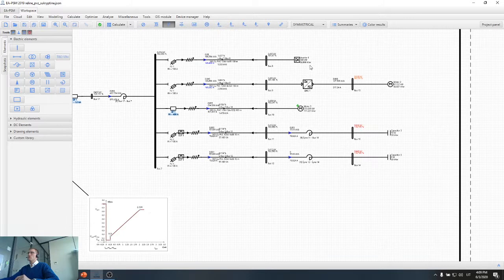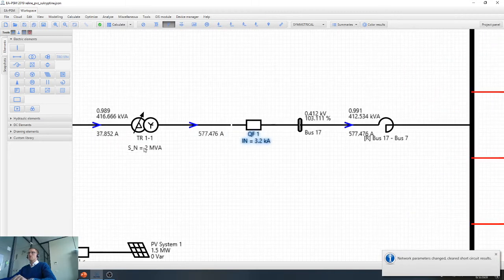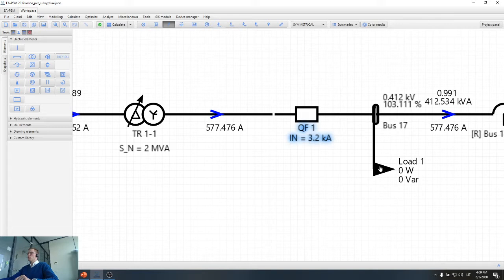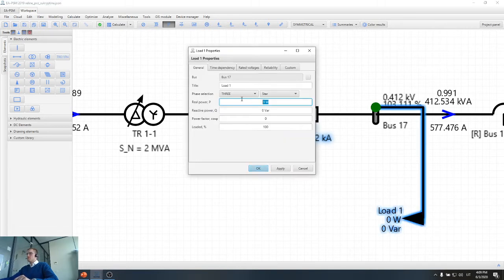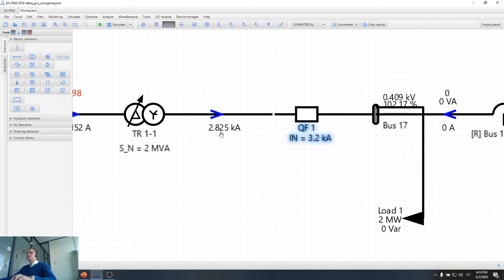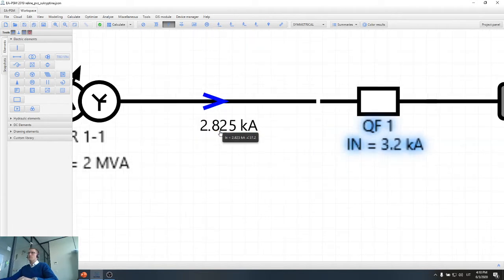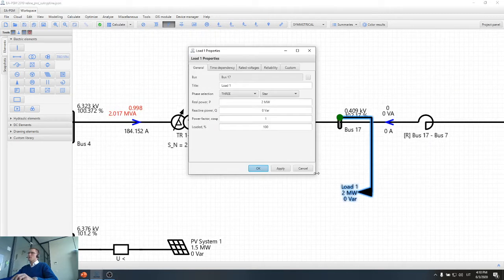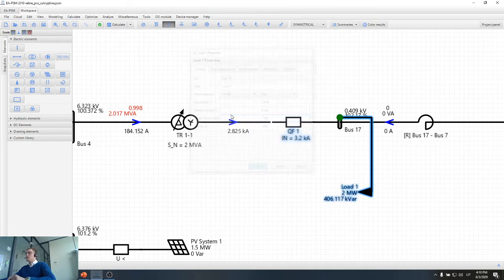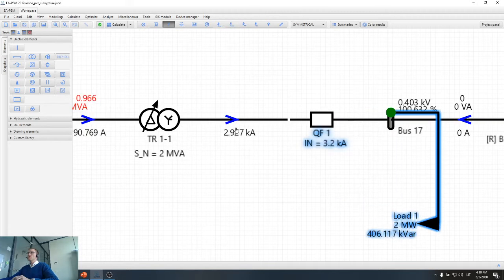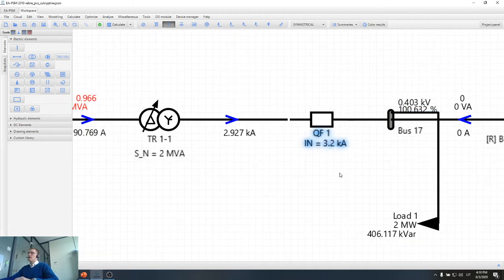This is because we have equipment which does not represent full loading of the transformer, and the breaker was selected by evaluating full load. So if I disconnect all this equipment, because the transformer is 2 megawatts, I will connect a lump load here and specify that this load is 2 megawatts. When I connect this lump load, I will see that current is 2800 amps if my transformer is fully loaded. However, if you evaluate some overload conditions as well, let's say I add some reactive power, current can reach about 3000 amps, and because of that we selected the breaker which is 3200 amps.